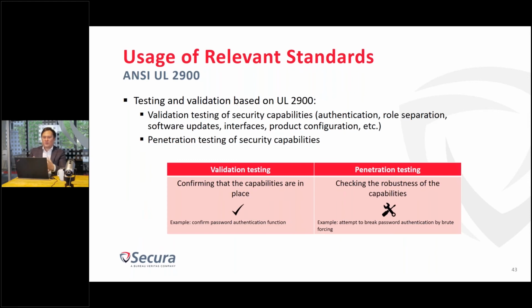A few examples. When we talk about testing and validation, we have been discussing validation and penetration testing. Let's explain a bit about how to demonstrate that the control, the security feature, is in place. For example, if you think about authentication, it will be a relatively simpler test to demonstrate that an unauthenticated user, or one with the wrong password, cannot access the device or the software. Well, keeping the same example of authentication, if we're talking about penetration testing, it goes one level deeper.